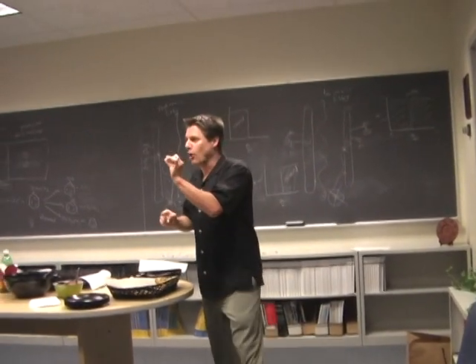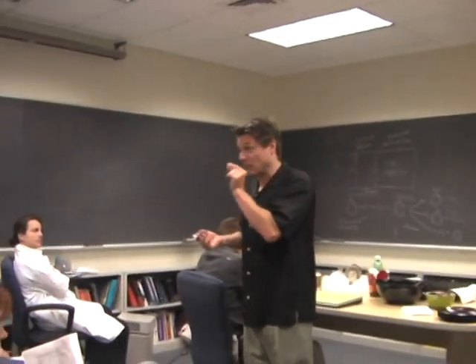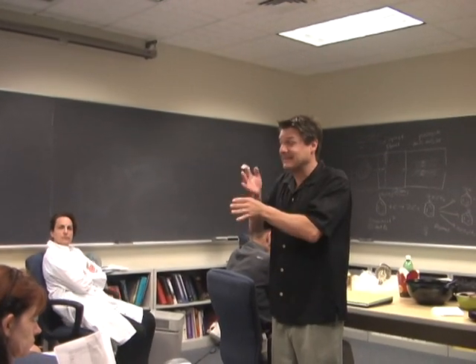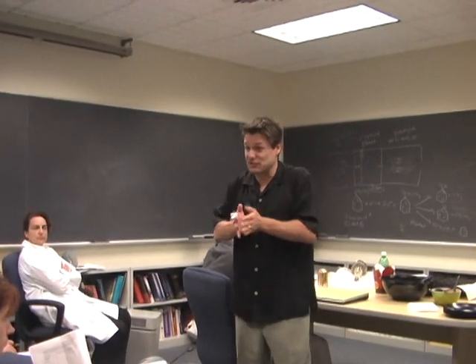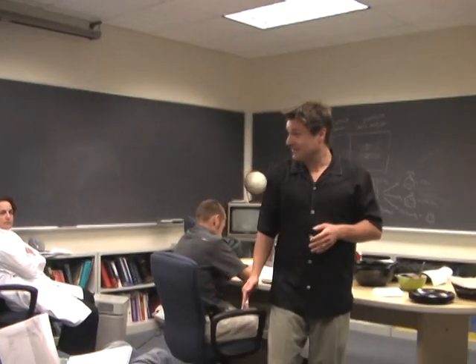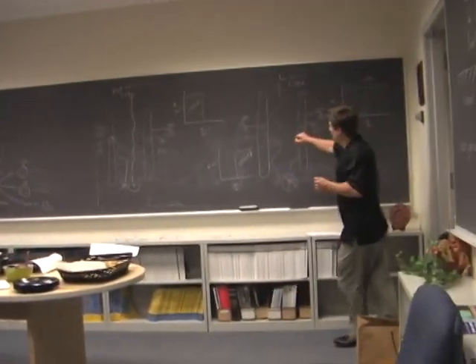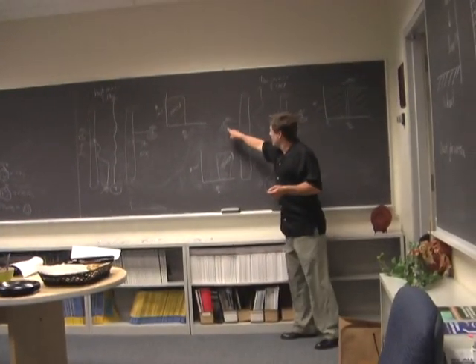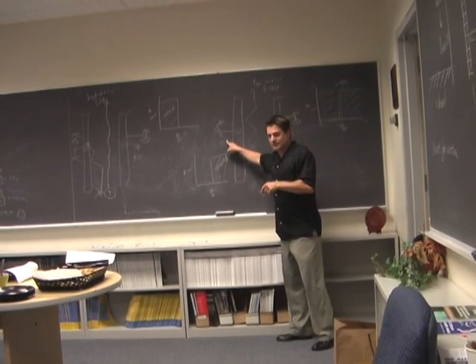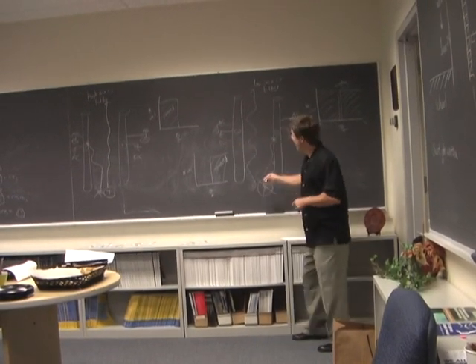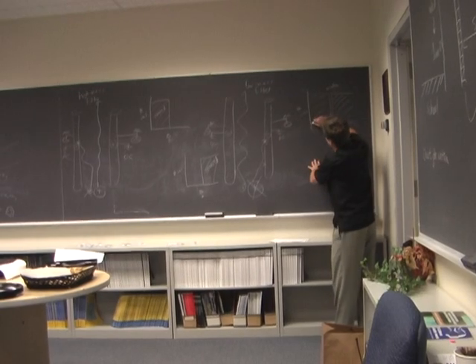My goal is to have the smallest window possible — maybe one Dalton or atomic mass unit, or less. There are some mass spectrometers that, if you're willing to spend enough money, can get it to several decimal places. You can actually separate isotopes — that's how sensitive it is. I'll change the ratio of the AC to DC voltage to maximize the device and ramp it from low to high — scanning.